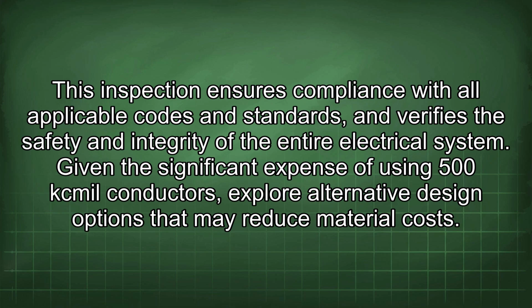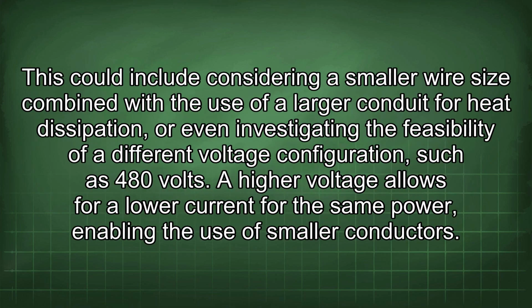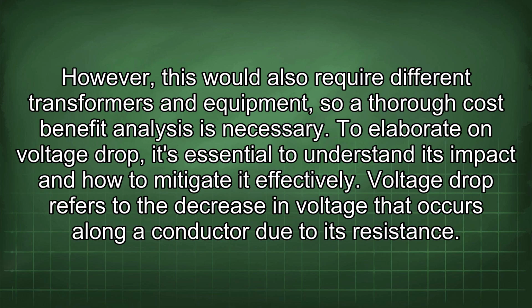Given the significant expense of using 500 kcmil conductors, explore alternative design options that may reduce material costs. This could include considering a smaller wire size combined with the use of a larger conduit for heat dissipation, or even investigating the feasibility of a different voltage configuration such as 480 volts. A higher voltage allows for a lower current for the same power, enabling the use of smaller conductors. However, this would also require different transformers and equipment, so a thorough cost-benefit analysis is necessary.